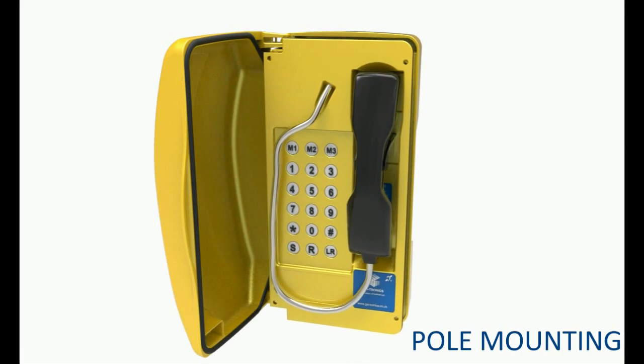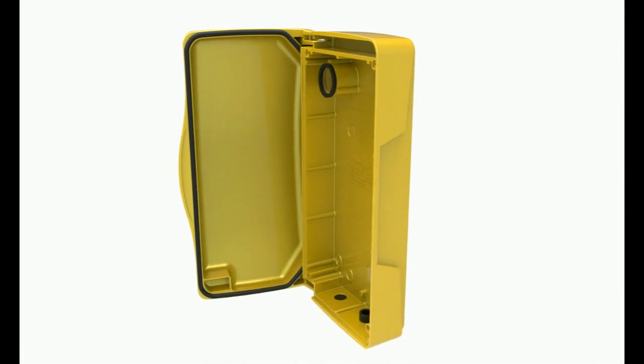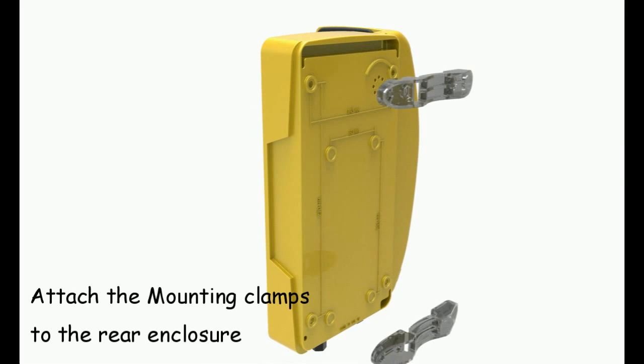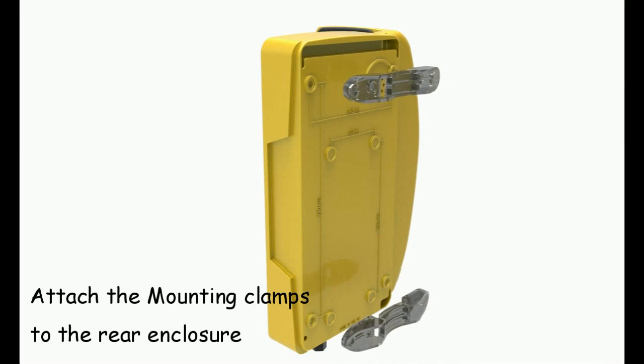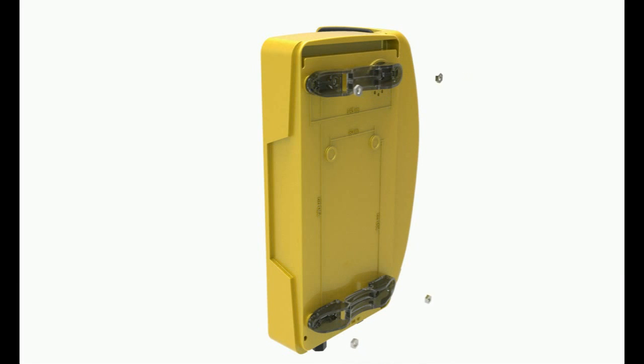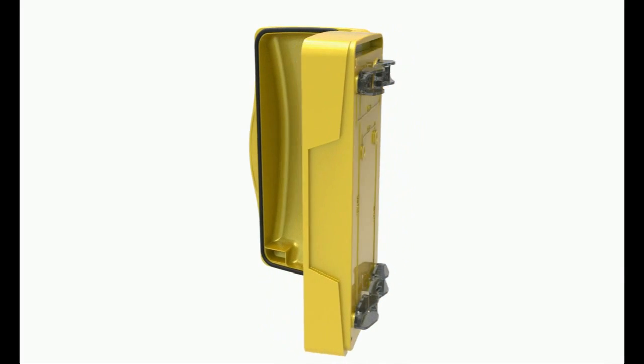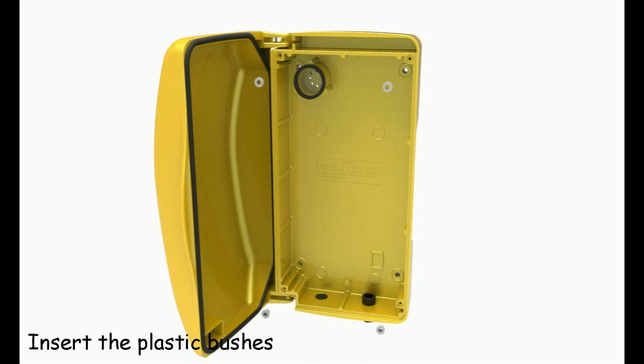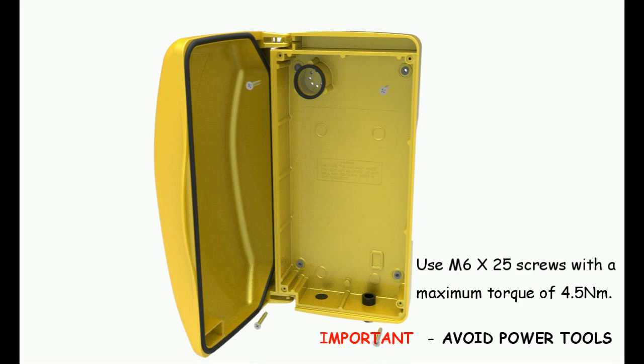Pole Mounting: Remove the faceplate. Attach mounting clamps to the rear enclosure. Insert the plastic bushes. Use M6 x 25 screws with a maximum torque of 4.5 Nm.